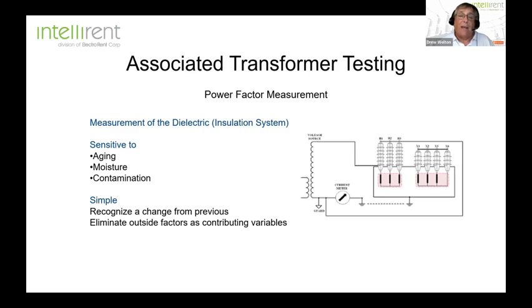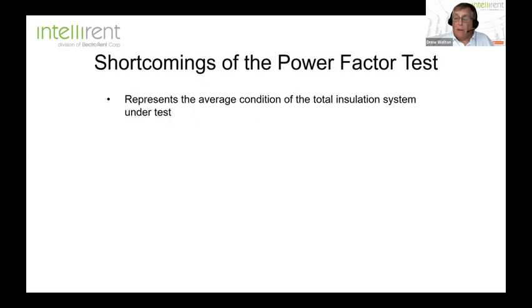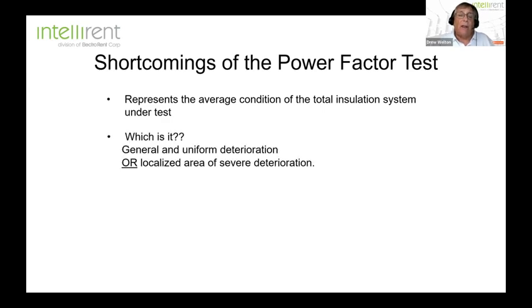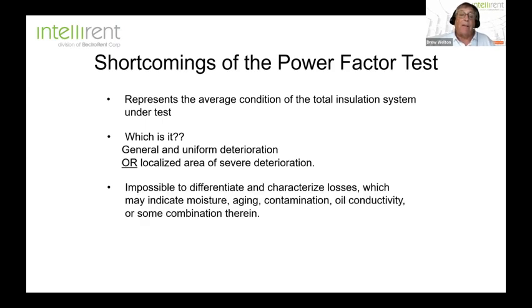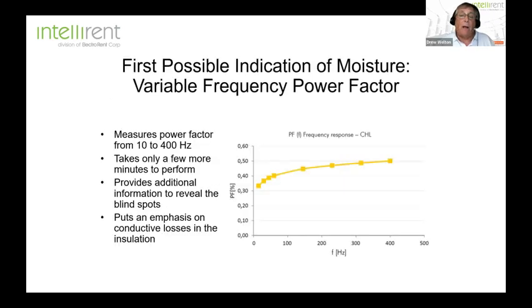And it's sensitive to aging, moisture, and contamination. But there's one problem with that, is that it represents just an average condition of the total insulating system under test. And we don't know by looking at those test results whether it's just general and uniform deterioration or if we have a localized area of severe deterioration.